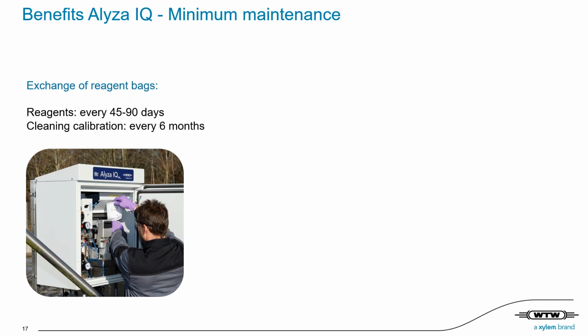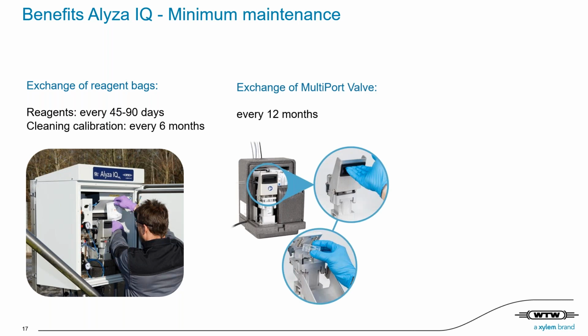Cleaning and calibration solutions have only to be exchanged every 6 months at a daily cleaning and calibration. As already mentioned, the main spare part of Alyza IQ is the MultiPort valve, which has to be exchanged only every 12 months. As you've seen before, just open the holder, take out the old one, replace it by a new one, and that's it.